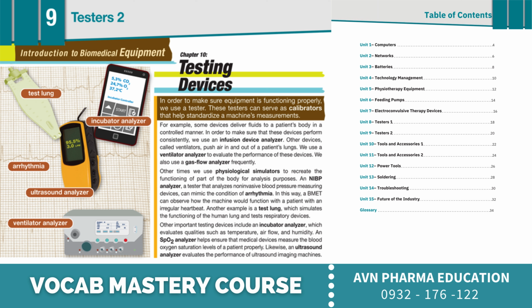Introduction to Biomedical Equipment. Chapter 10. Testing Devices. In order to make sure equipment is functioning properly, we use a tester. These testers can serve as calibrators that help standardize a machine's measurements. For example, some devices deliver fluids to a patient's body in a controlled manner. In order to make sure that these devices perform consistently, we use an infusion device analyzer.